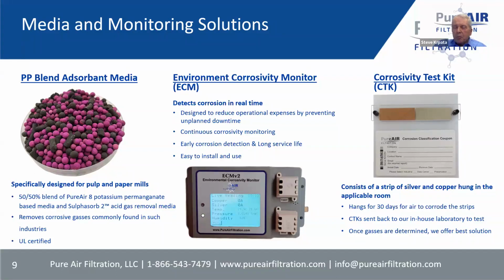The purple in the PP blend has a color change that tells you it's being used up, and it gets used up in the direction of airflow. So in that industrial VBS we showed earlier, which has bottom-up airflow, the bottom media of the bed gets used up first, and the top gets used up last. Knowing that, if you take samples throughout the bed, you can see if it's still viable or not.